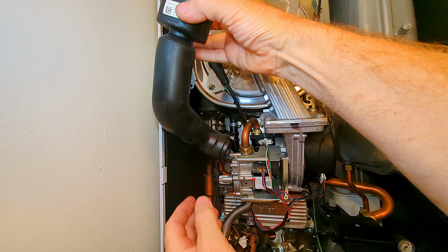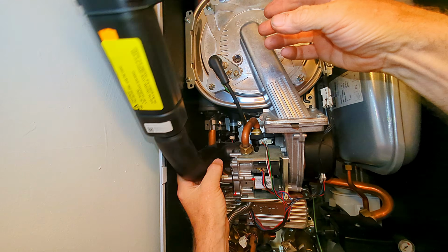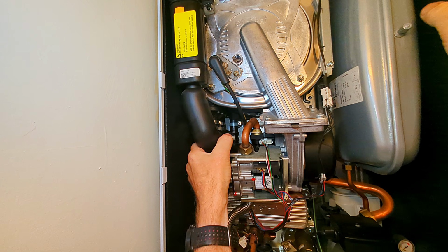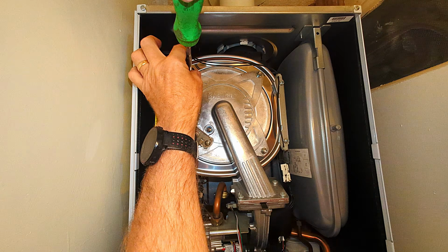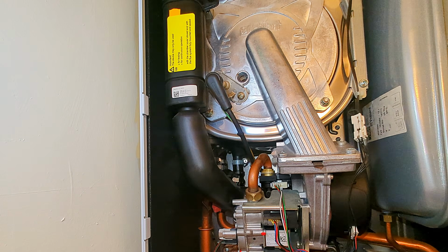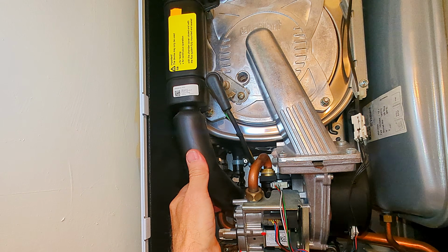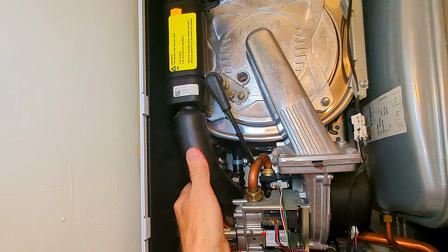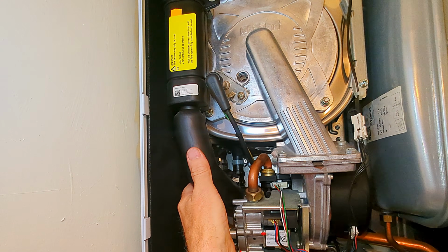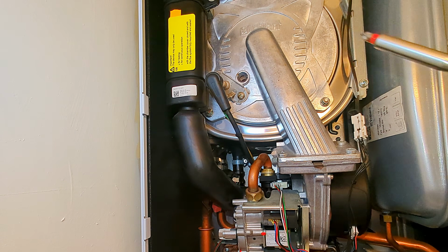Now I just need to refit the air intake. I push it onto the gas valve, fold it into position, and do up the screw. As I'm doing up the screw, I always push against the air intake, making sure it stays properly located on the gas valve inlet, because I do sometimes come across boilers where it hasn't been properly located, which affects combustion of the gas - obviously bad.